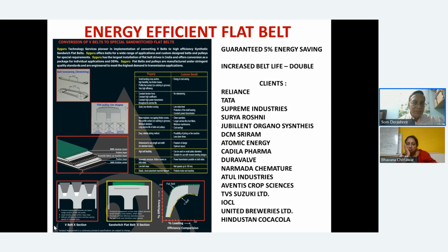And the third is, you see the thickness of this material, V-belts, where a set of, let's say, three of them have to be bent. And if it is, let's say, 1500 RPM, then almost 15 into 4 times it has to be bent and wound around the pulleys again, along with the wedging in action. Compared to a very thin flat belt system, you will find that the saving between the V-belt and flat belt is the efficiency gain. Again, 5% is what is guaranteed. A lot of clients, including Reliance, Tata, etc., we have done. We've been doing it regularly here.